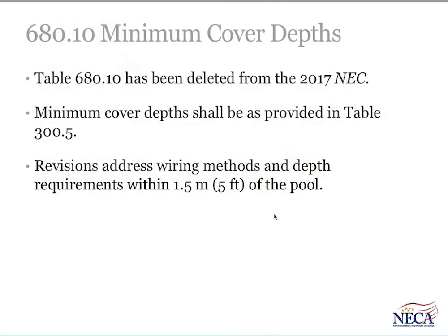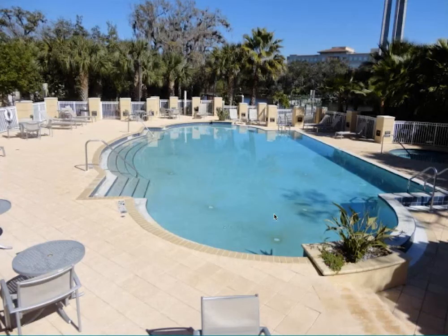Article 680 covers swimming pools and other similar bodies of water. And 680.10 has been a long-standing requirement in the NEC, covering specific burial depths for conduit and wiring methods that are installed within the vicinity of the pool. Panel 17 acted favorably to remove that because the wiring depths were effectively covered by Article 300, and specifically Section 300.5. So we no longer have the same requirement that appears in both locations.